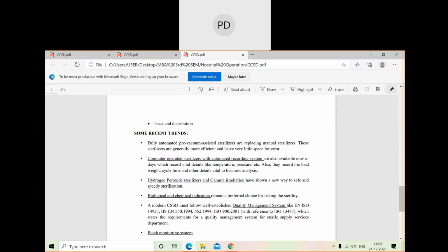And biological and chemical indicators remain the preferred choice for testing sterility. You know what happens, there are two patches. One is considered biological and the other is called the chemical indicator. When you pack the trays, on top of that you write the batch number and put the particular stickers, one biological and one chemical. When you put it inside the sterilizer, the color changes for these two indicators. If the color change doesn't happen, that means it did not get sterilized properly. So then you have to put that tray in again.